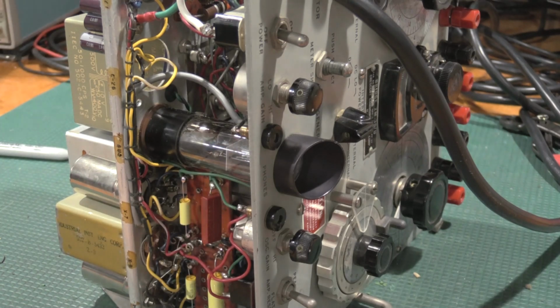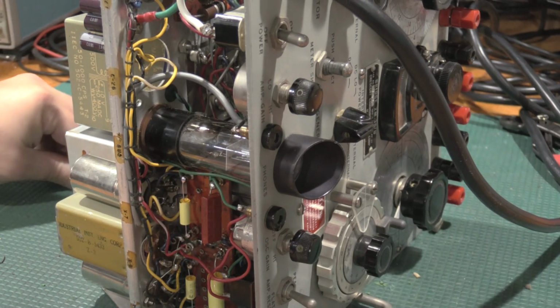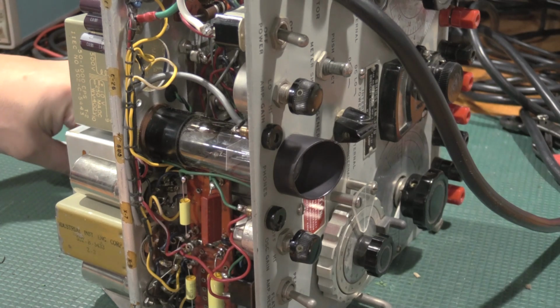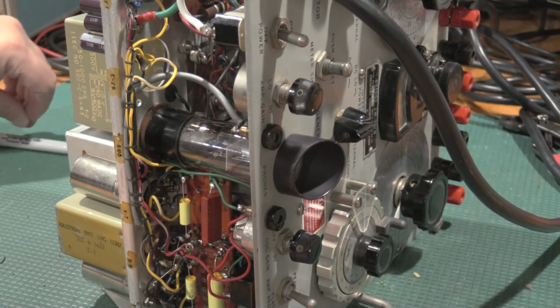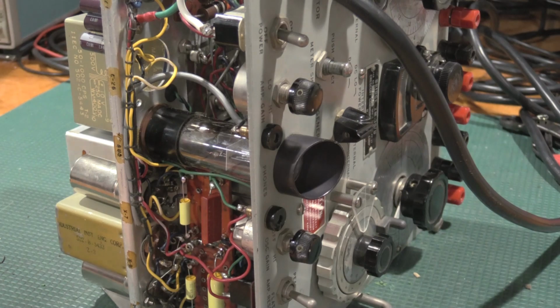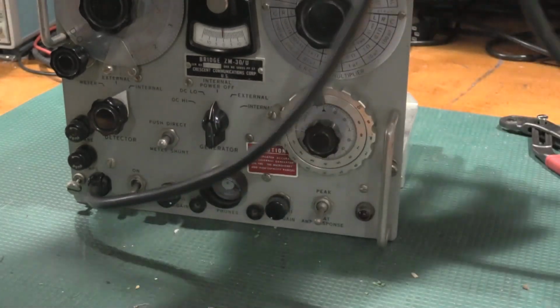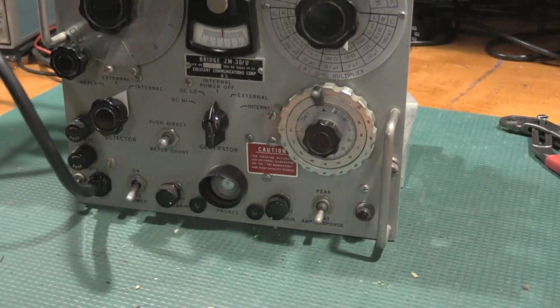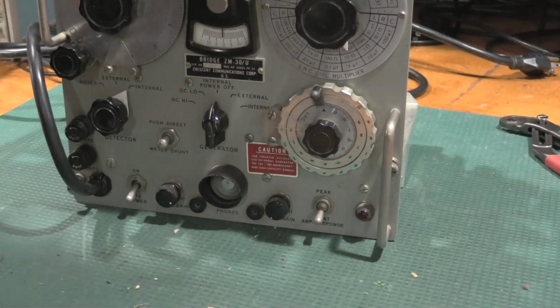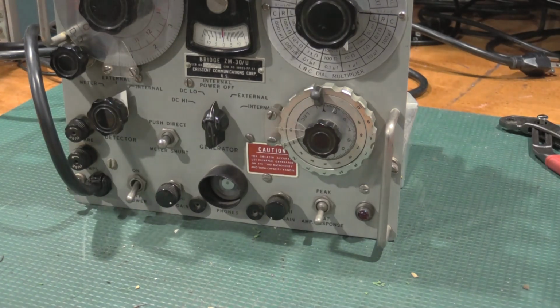So let's see if we get smoke. We are going to start this on the current limited Variac supply, because these capacitors haven't seen voltage, and this unit hasn't seen voltage in a very long time. That'll tell us how healthy everything is, and if we wired anything wrong and it's shorted out, which would be a bad day. Let me get that all set up and I'll bring you guys back.